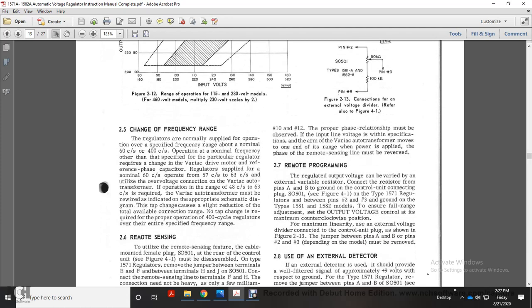Change of frequency rating. The regulators normally are supplied for the specified frequency rating, with a nominal of 60 cycles to 400 cycles a second. Operating with a nominal frequency other than specified for a particular regulator requires a change of the variac driver motor reference-phase capacitor. Regulators supplied for a nominal 60 cycles can operate with a 57 cycle to 63 cycle range. Utilize the over voltage connection of the variac automatic transformer. If an output range of 48 cycles to 63 cycles is required, the variac autotransformer must be rewired, as indicated in the appropriate schematic diagram. The tap changes should use a slight reduction of the total available correction range. No tap change is required for proper operation of 400 cycle regulators over the entire frequency range.